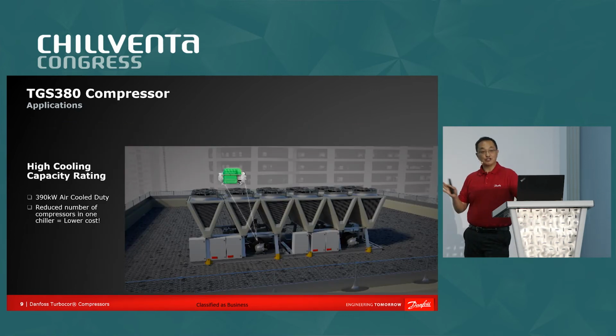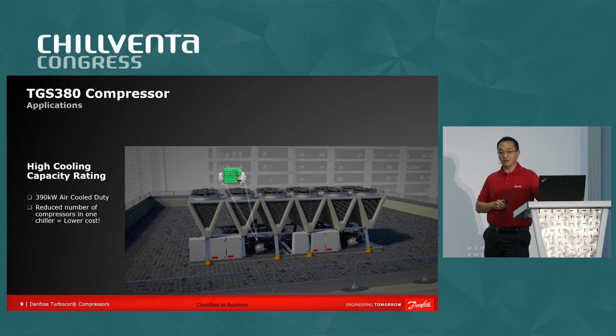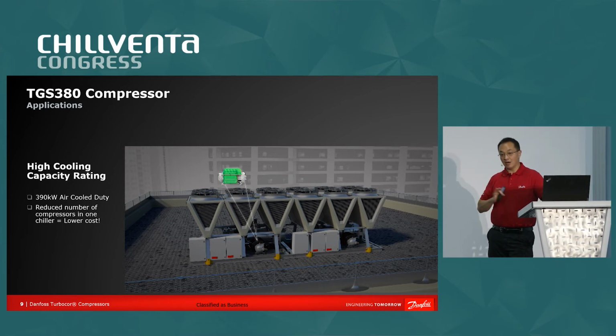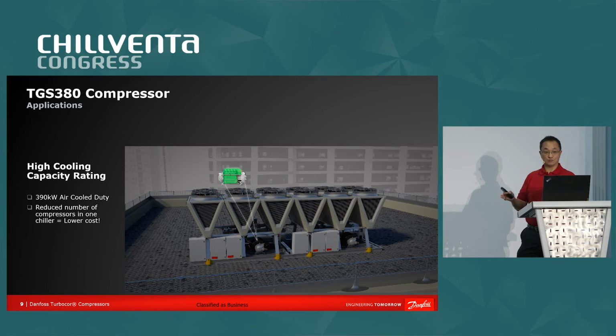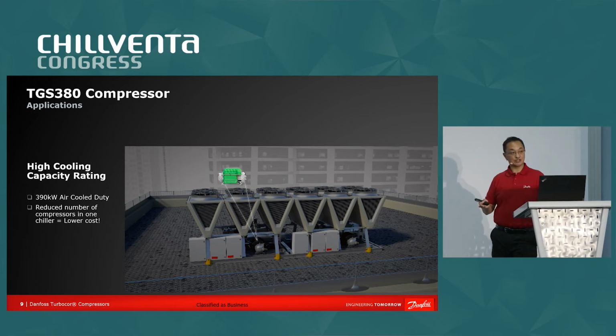I mentioned earlier that this compressor is very suitable, or optimized, for air-cooled chiller applications. High capacity, up to 390 kilowatts of nominal cooling. This high capacity rating gives customers as well as OEMs an opportunity to lower their costs, because you can get more cooling capacity out of one compressor. So this gives you the opportunity to reduce the number of compressors in your configuration and fit more cooling capacity with fewer compressors, thereby reducing the initial cost of your chiller.